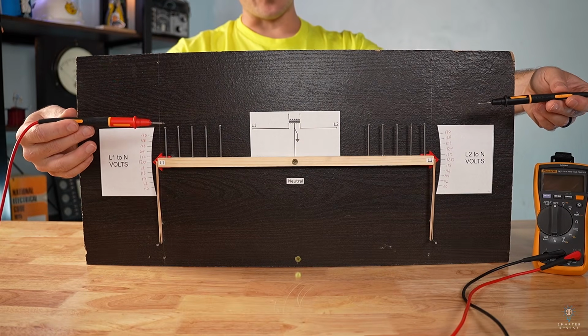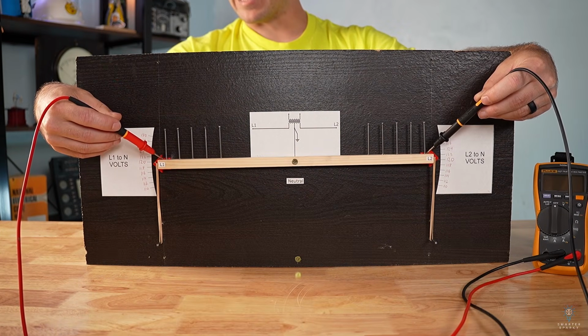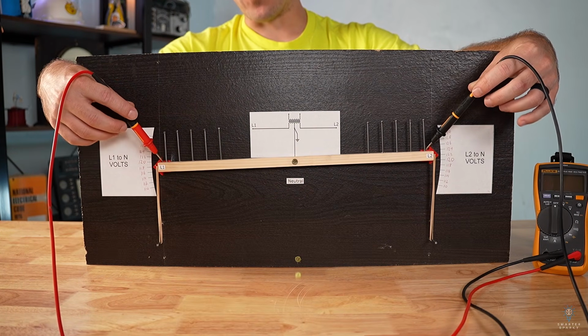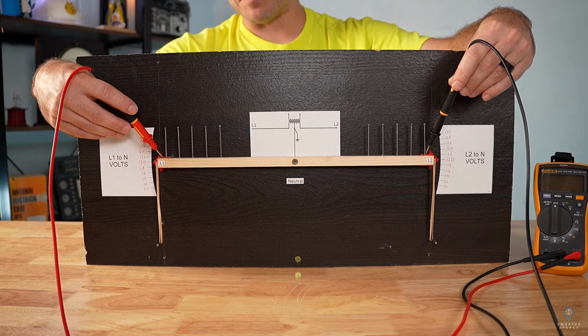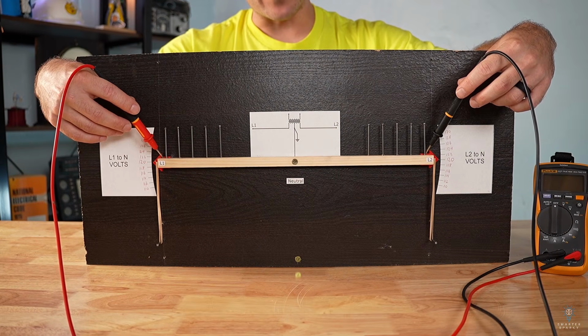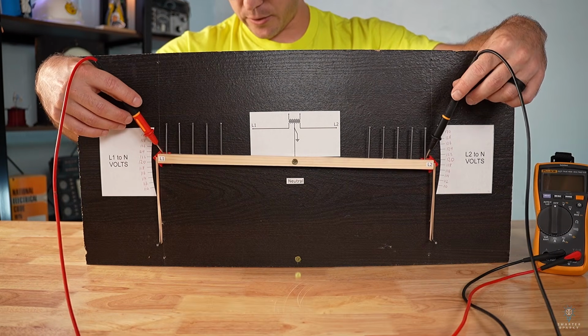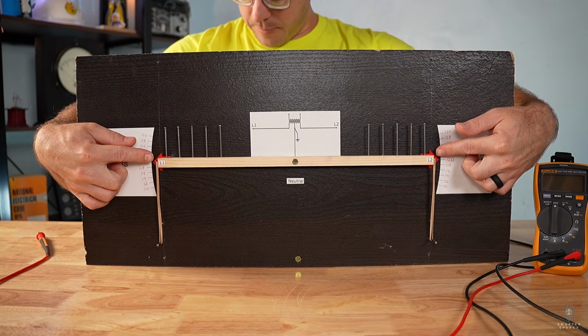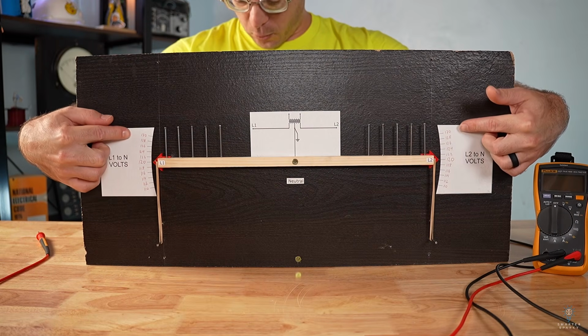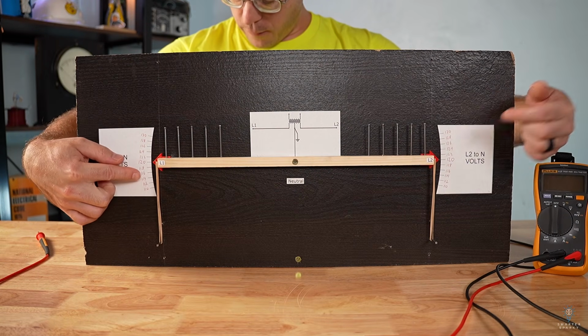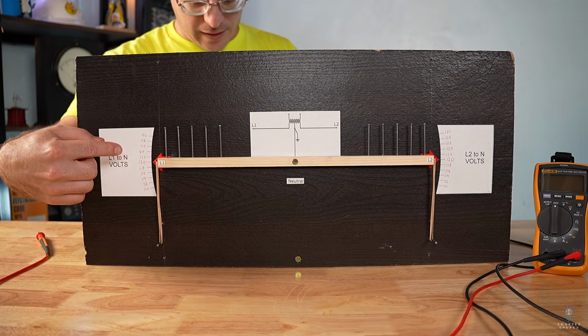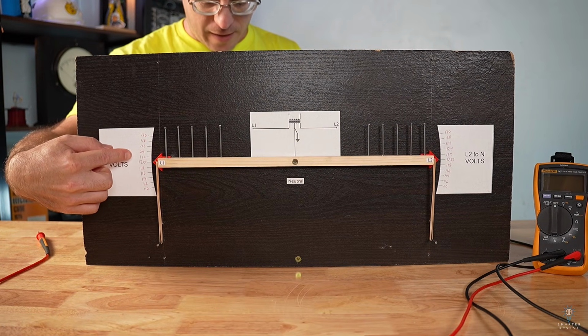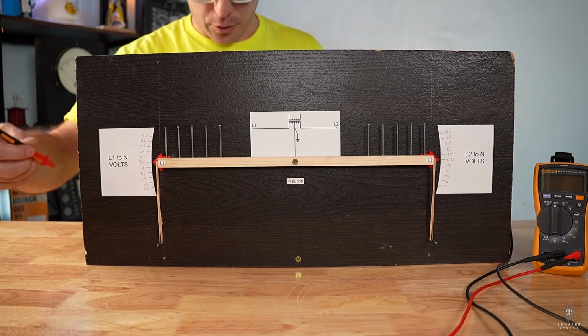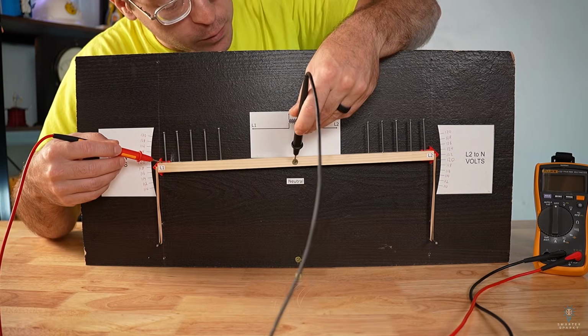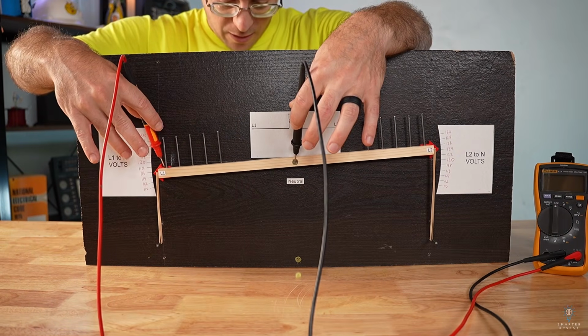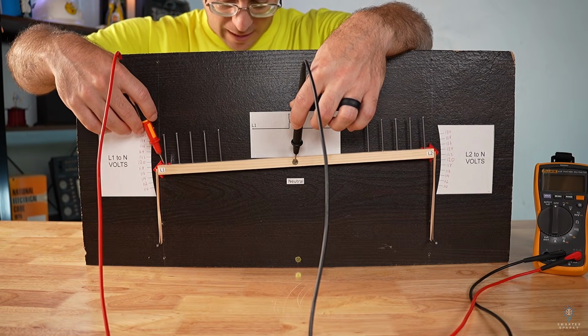So we can imagine if we took a voltmeter and measured from line 1 to line 2, we'd measure 240 volts regardless of how this beam tilts. There's still going to be 240 volts from line 1 to line 2. The arrows on the end of the beam are going to show the relative voltage to neutral from that line.